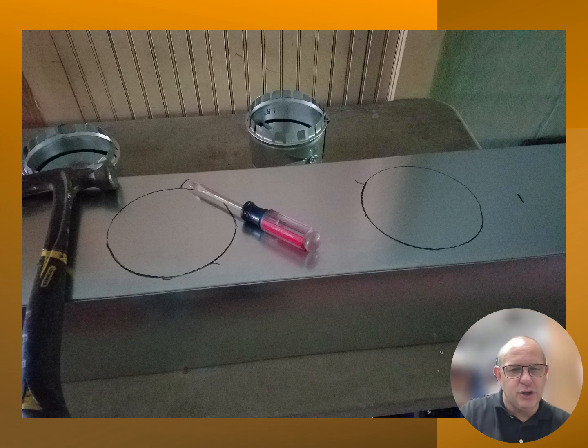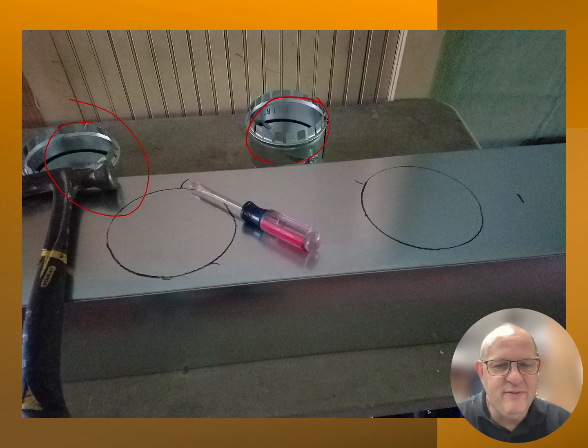Now I've drawn the circles for the takeoffs. I've got my two takeoffs sitting down there, and you can see them in this location. Then I brought out what I use to put the holes into the ductwork, which is a bad screwdriver and a hammer. I will pound a hole into the ductwork, as you will see in the next slide. You can use any type of drill bit to put a hole in there, but I have found that it is easier to use a screwdriver and a hammer to give me the hole, and then I use my aviation snips to go around the hole and cut it perfectly to fit that damper that we have placed on it.